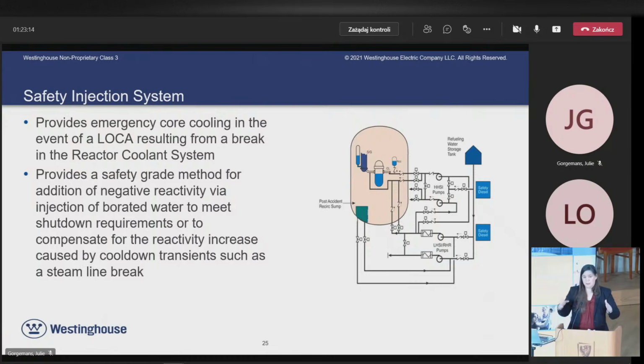Because we need to inject from 150 bar to basically 10 bars, we need to have different pumps, because it's difficult to design a pump to operate over such a large range of pressure. That's why we have what we call high-head and low-head pumps. We have redundancy, of course, on the systems, and we also have a lot of support systems that are required. We need to provide electricity to power those pumps reliably, so that means with backups on site. We need to provide the instrumentation and controls, which will ensure that the pump is delivering the amount of water that it needs.